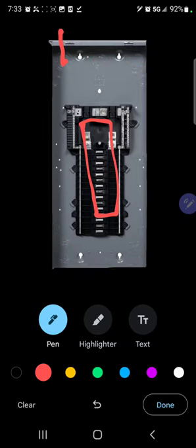I've actually heard horror stories of inspectors making people set junction boxes up above panels, work this wire back up in the junction box, and then work the extended wire back on the panel. But that is just overkill and very unnecessary. This whole apparatus here, you could take these guts out, which is the panel. You could take these guts out, and this is just a very large junction box. So to answer the question, yes, you can splice inside of a panel, and it's the preferred place to splice. It is really just a large junction box.